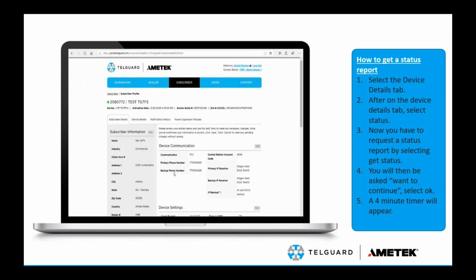And then we would send that event that zone or that output is programmed for within the panel to your central station. So at that point, you get the trouble signal, you're wondering what's going on with my unit, because typically that trouble signal is very broad. It's not very specific due to the fact that our STC relays monitor multiple troubles. So you get a trip of that output or that zone. The next step would be to come to Telguard.com and get a status report.